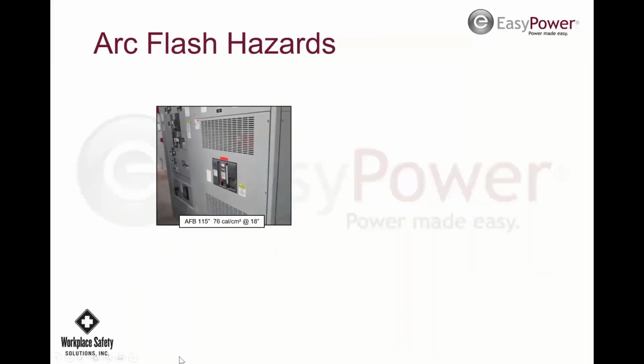Okay, here's a study that was done. This is an interesting study. This company bought a facility that was an older facility because they grew out of the one that they had. The facility they had was installed in 1962. They had 4,000 amp switchgear and a bunch of 480 volt panels and all kinds of stuff through the facility. They decided they were going to replace it, and they didn't need 4,000 amps for their particular loads. So they put in a 1,500 amp switchgear, like you're looking at right here, and replaced all the infrastructure inside with new electrical equipment as well.